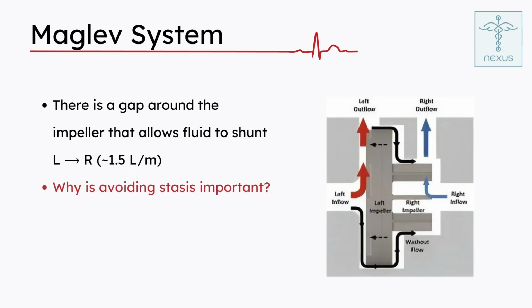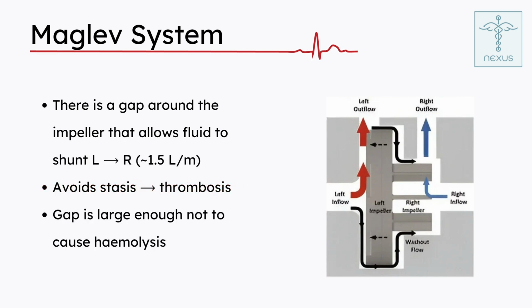The genius of the design is that it actually wants to have that. The reason is because if you have stagnant blood around the side, what do you get? Clots, right? So you want to avoid clot formation around the edges of the impeller, and they actually design it to have a decent amount of blood flowing around the sides.